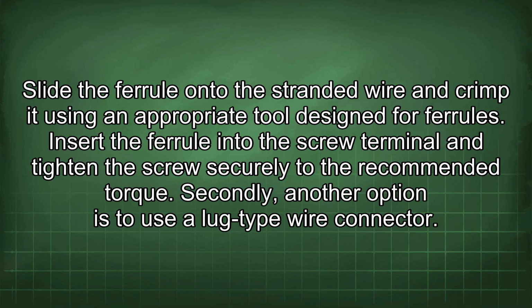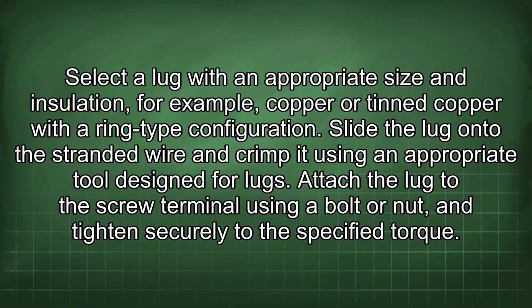Secondly, another option is to use a lug-type wire connector. Select a lug with an appropriate size and insulation, for example, copper or tinned copper with a ring-type configuration. Slide the lug onto the stranded wire and crimp it using an appropriate tool designed for lugs. Attach the lug to the screw terminal using a bolt or nut and tighten securely to the specified torque.